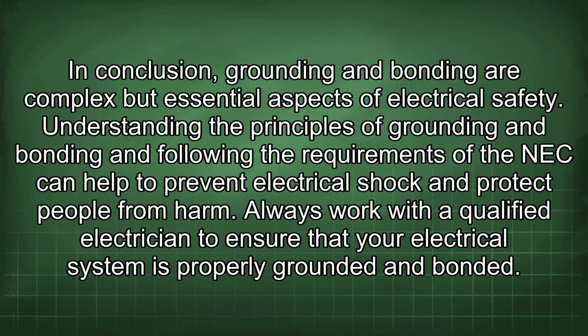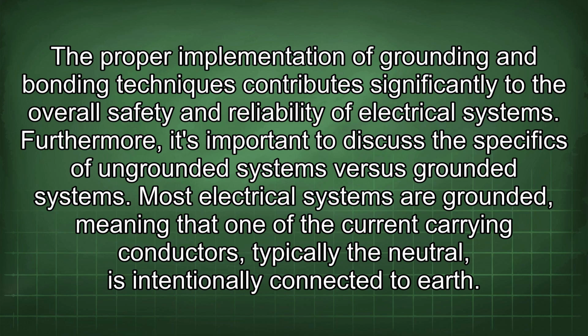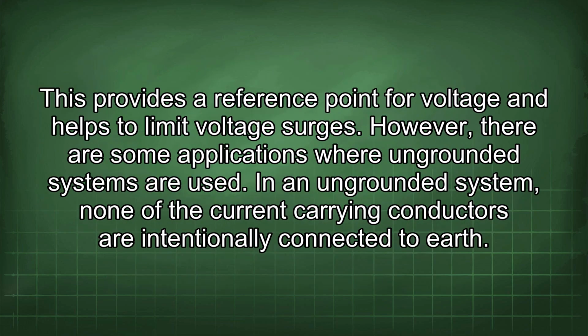Always work with a qualified electrician to ensure that your electrical system is properly grounded and bonded. The proper implementation of grounding and bonding techniques contributes significantly to the overall safety and reliability of electrical systems. Furthermore, it's important to discuss the specifics of ungrounded systems versus grounded systems. Most electrical systems are grounded, meaning that one of the current carrying conductors, typically the neutral, is intentionally connected to earth. This provides a reference point for voltage and helps to limit voltage surges.